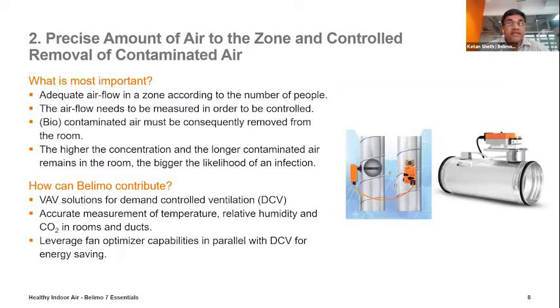Now, whether we are exactly sending that much amount of CFM or the number of air changes, that also needs to be measured in terms of doing the better control. Contaminated air must be removed consequently, or maybe it should be diluted. Higher the concentration, longer the contaminated air remains in the room, bigger is the likelihood of an infection. This we have seen in most of the hospitals, most of the contaminated areas, and I have seen a lot of changes in the HVAC design in the last 2 years based on this.